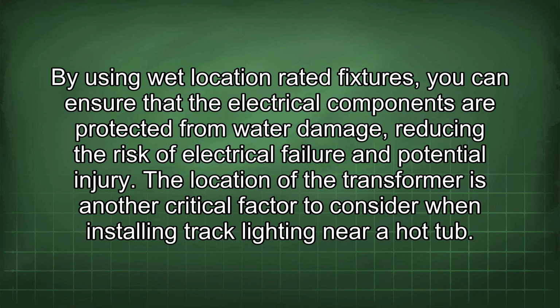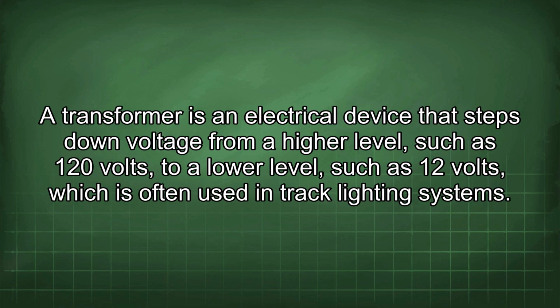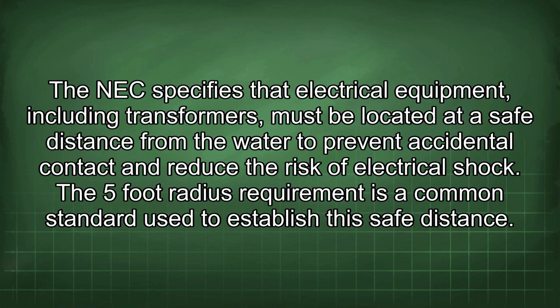The location of the transformer is another critical factor to consider when installing track lighting near a hot tub. A transformer is an electrical device that steps down voltage from a higher level, such as 120 volts, to a lower level, such as 12 volts, which is often used in track lighting systems. The NEC specifies that electrical equipment, including transformers, must be located at a safe distance from the water to prevent accidental contact and reduce the risk of electrical shock. The 5-foot radius requirement is a common standard used to establish the safe distance.